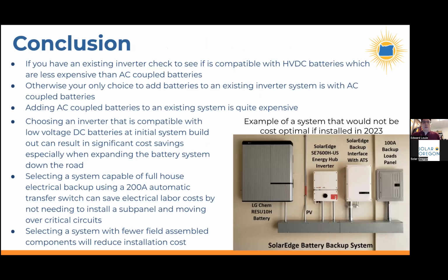So some conclusions from this slide deck: if you have an existing solar system, check if it's compatible with high voltage DC batteries. If it is, adding high voltage DC batteries to that compatible inverter is less expensive than adding AC coupled batteries. If it's not compatible, your only option is AC coupled batteries, which are more expensive—though there are still many reasons to do it. In a new system, adding AC coupled batteries is quite expensive, so if you're building a new system, consider an inverter compatible with low voltage DC batteries, since there are significant cost savings in doing so.